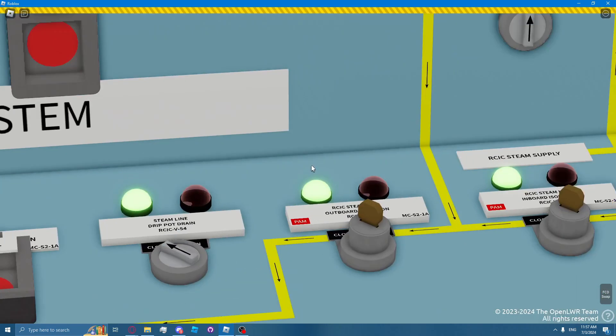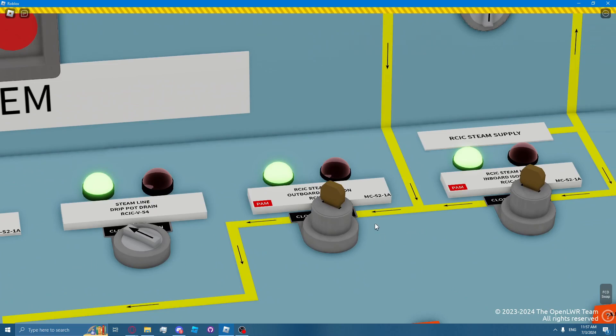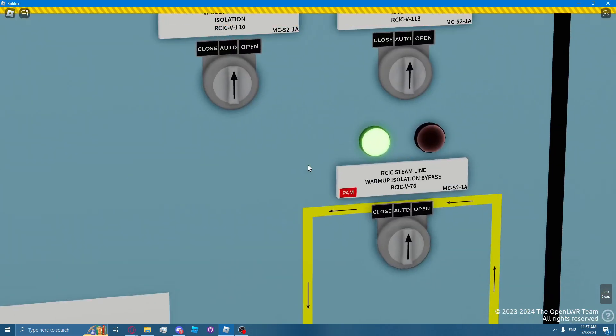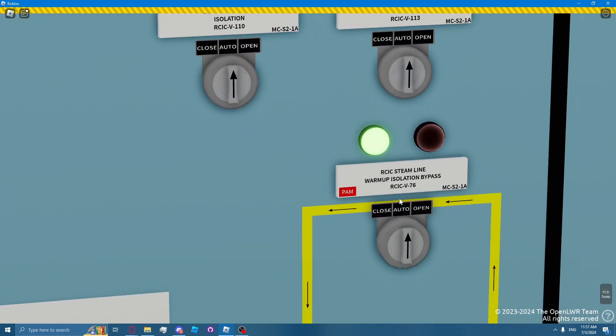When the RCIC system isolates, the inboard and outboard isolation valves close, RCIC valve 8 and RCIC valve 63, and the warmup isolation valve, RCIC valve 76, closes.